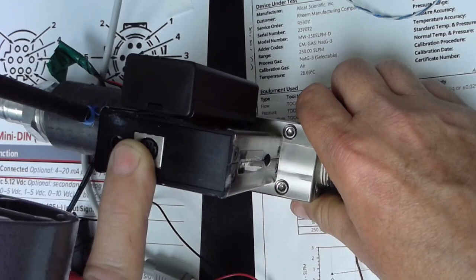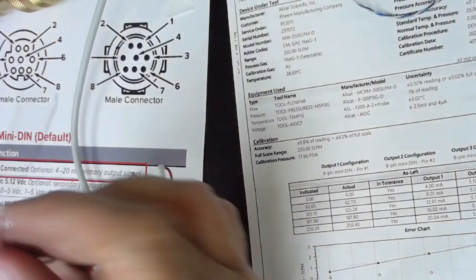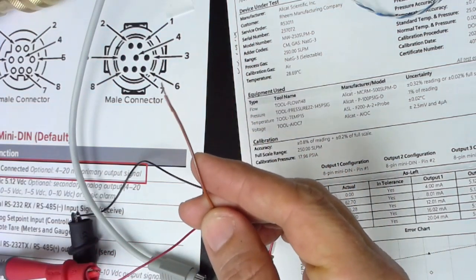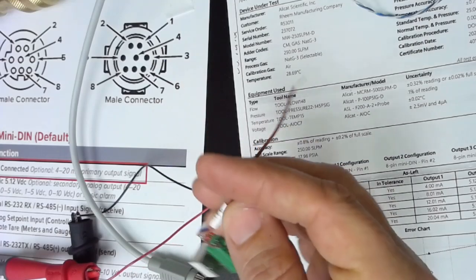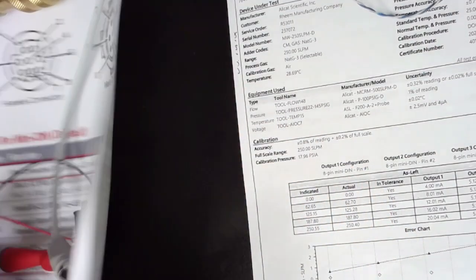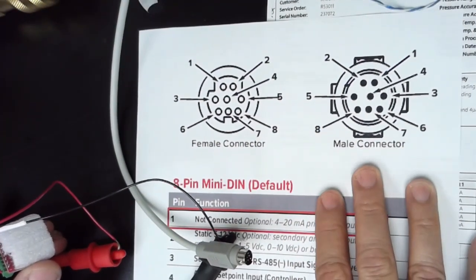We're going to unplug the cable out of the existing Alicat. The Alicats are not loop powered; they have a separate 24 volt pin, so you can use this adapter for troubleshooting. If this is hooked up correctly, I should have 24 volts on this pin right here. The pin out is provided in the manual. I have a picture of it right here, in the same container as this little adapter.